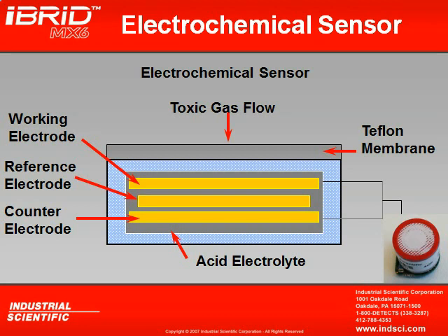And whether an electrochemical sensor is sitting on the shelf or sitting in the instrument, it's degrading at about the same rate. So this is one reason why we always recommend that you calibrate your instrument once a month. We know that inside that sensor, those metal plates are under assault by the acid. We know that inside there the chemicals are changing. Therefore, monthly calibrations are a necessity to ensure that the output current is being adjusted by the instrument's electronics to compensate for any lost signal over time.